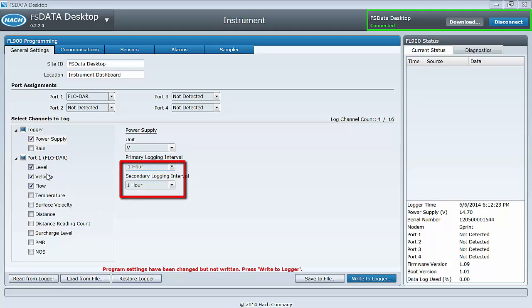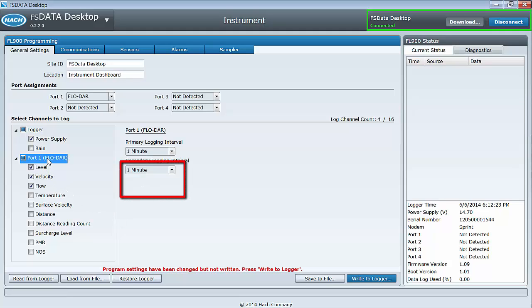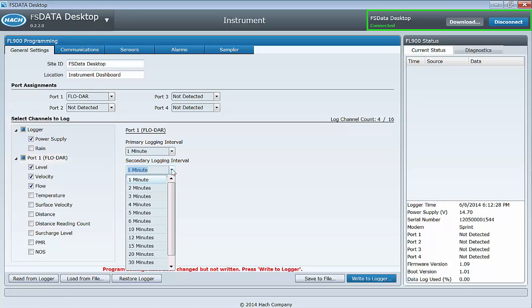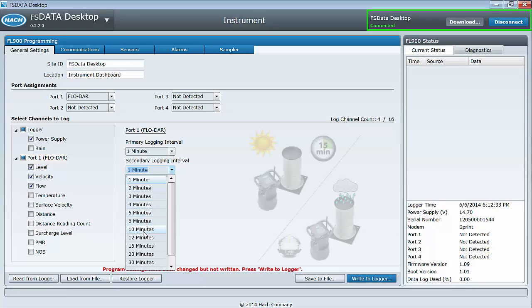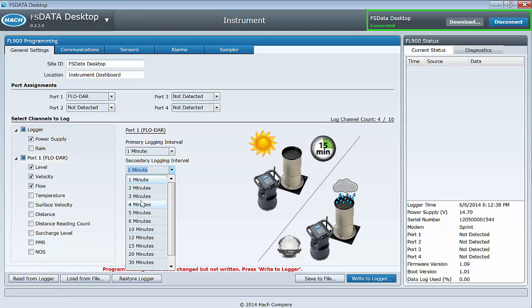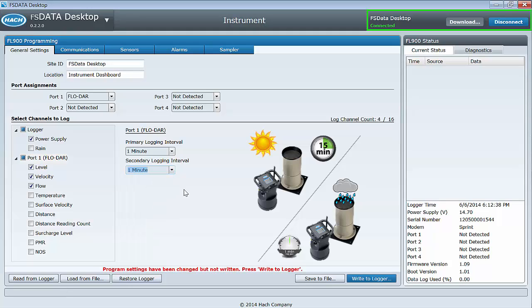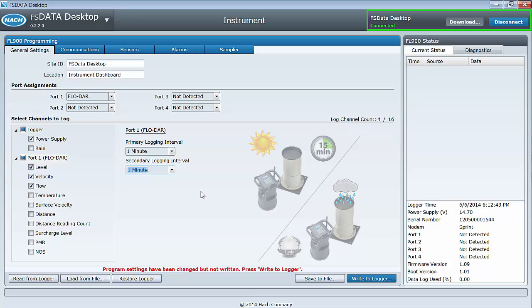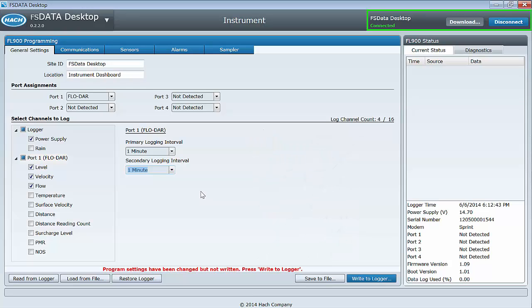The secondary logging interval need only be set if you want to use the dynamic data logging capability of the instrument. This feature can change the data logging interval triggered by an alarm condition. For example, if you want to collect data more frequently during a rain event, you can set a trigger to use a shorter logging interval when a rain alarm is activated. We will discuss setting these triggers when we talk about the alarms tab.